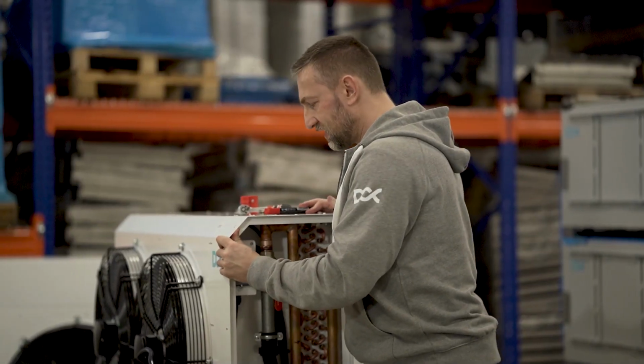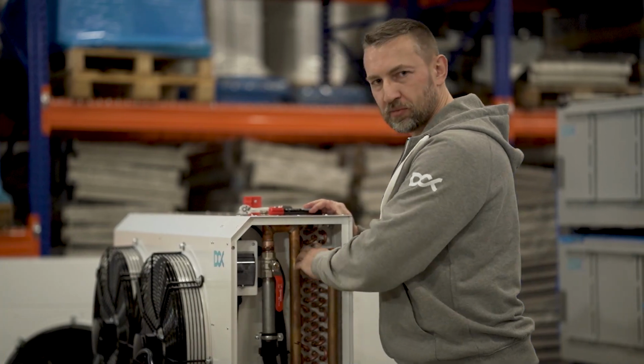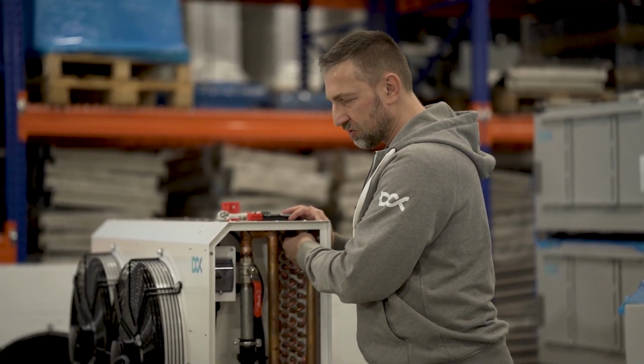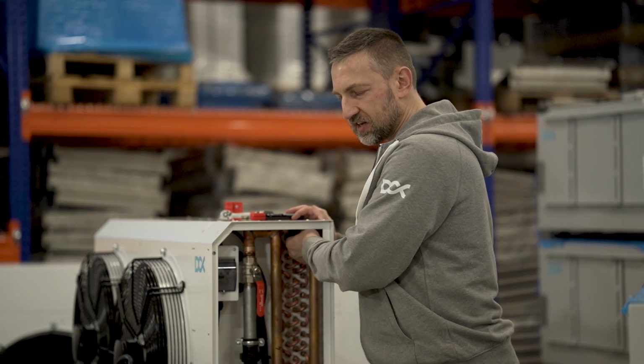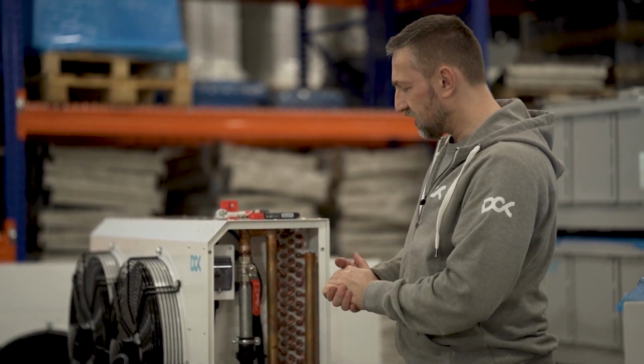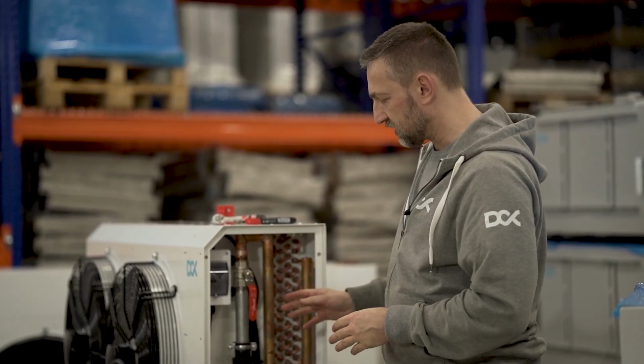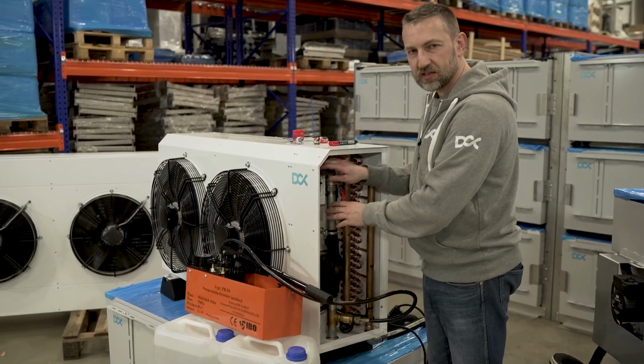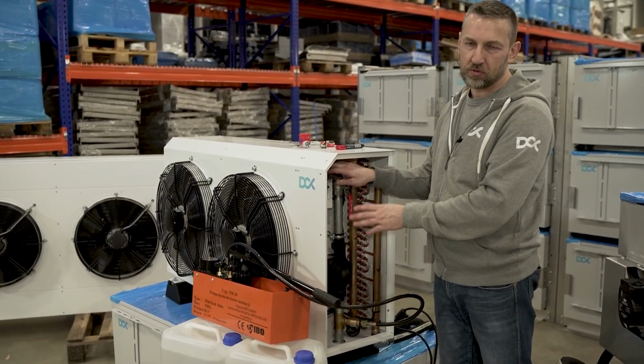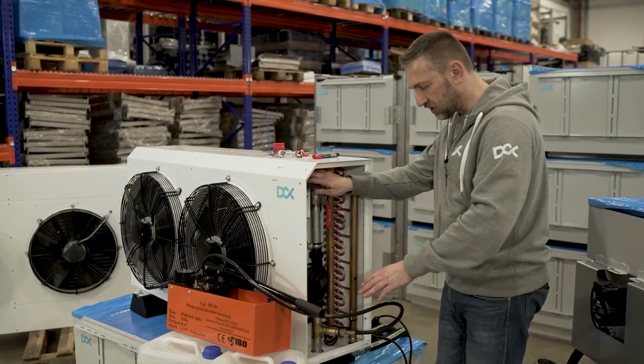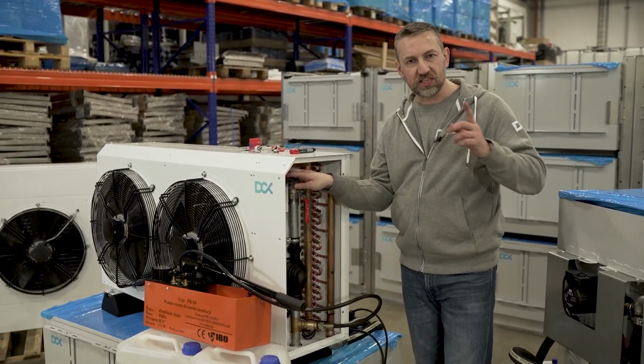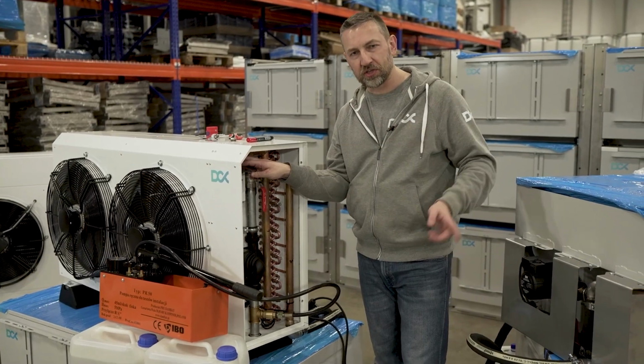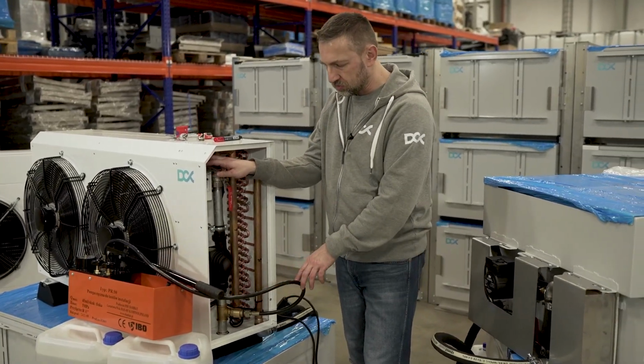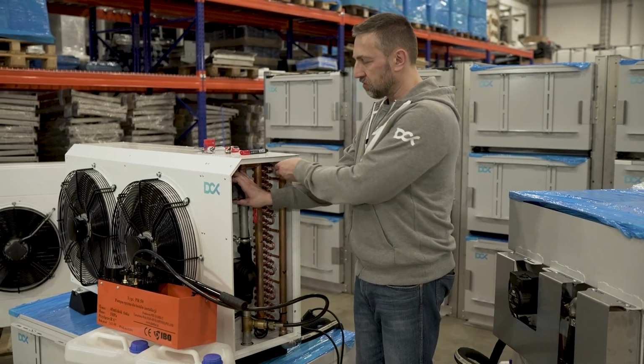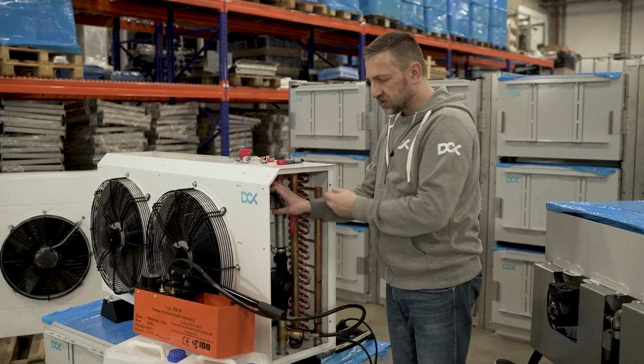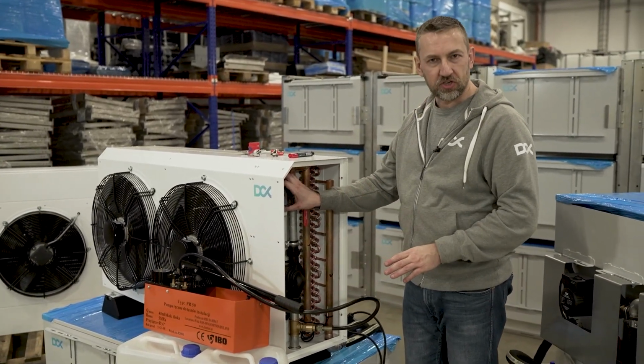It will allow the air to escape from all those coils. So you can use that, and then you can get some of the air from the system. So the pump will be so silent that you will not hear the operation, or almost not hear the operation. If you hear any air traveling through the system, so whooshing, bubbles going to the coil, it means that you just need to open the air vent just a little bit, regulate it, release some air, just be patient, right?